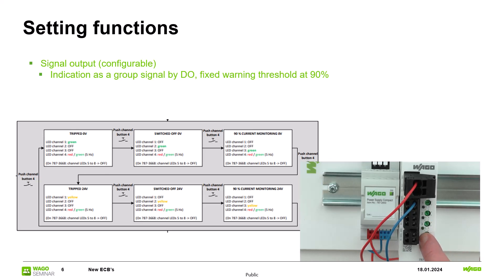By pressing button 4 again you can use the digital output exactly the other way around. Channel 1 now lights up orange which means that the digital output jumps from 0 to 24V if the channel has tripped. Channel 2 lights up orange which means that the digital output jumps from 0 to 24V if the channel has tripped or switched off.